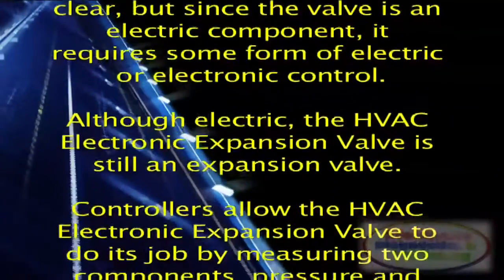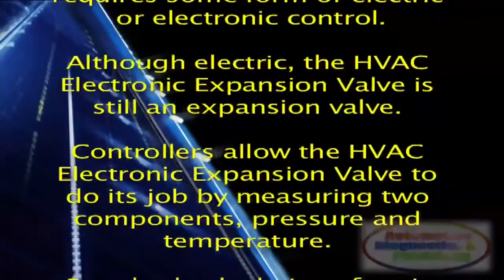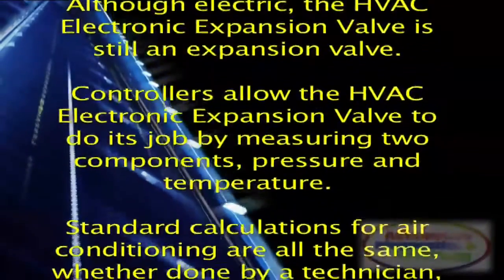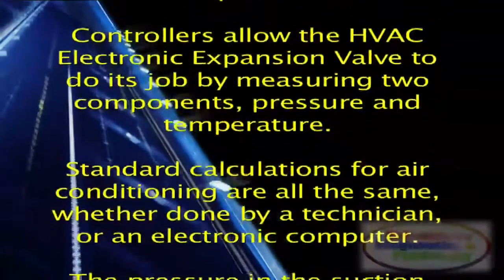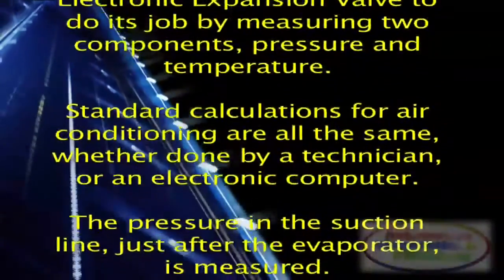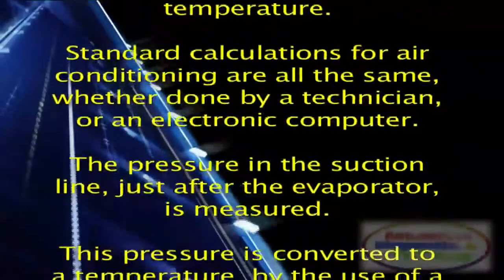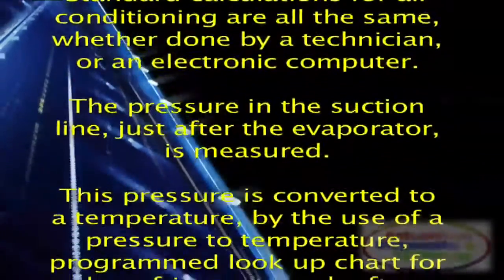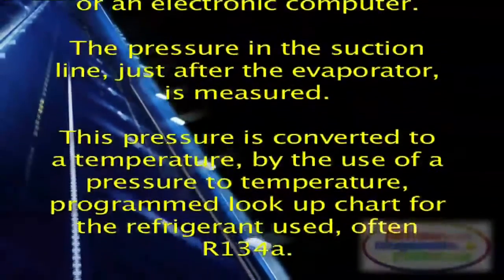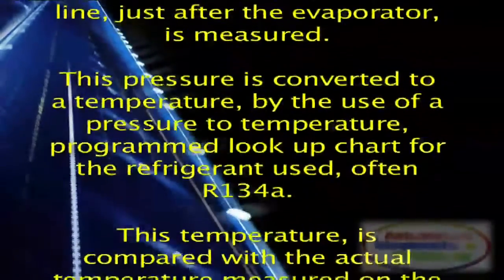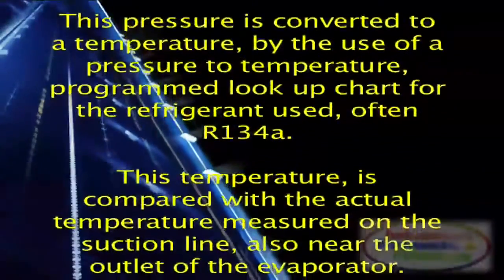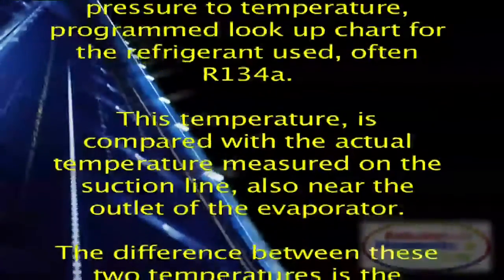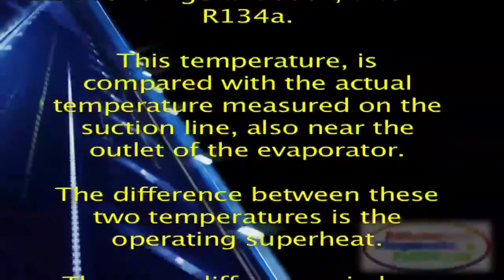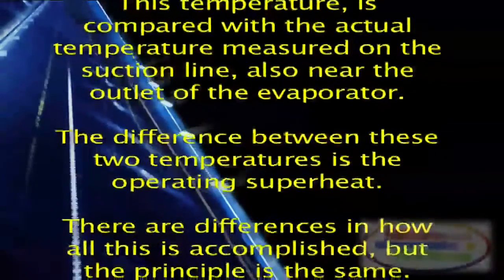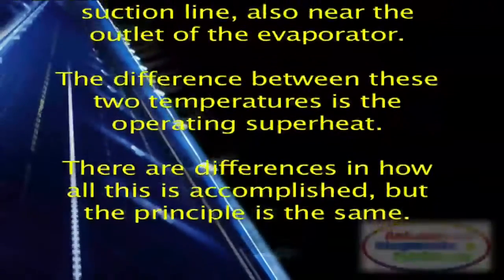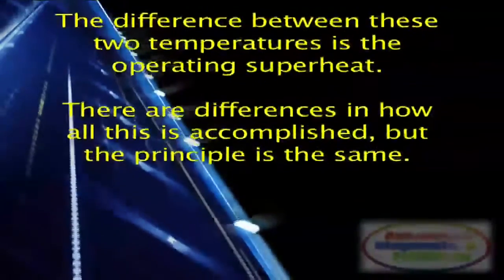Controllers allow the HVAC electronic expansion valve to do its job by measuring two components, pressure and temperature. Standard calculations for air conditioning are all the same, whether done by a technician or an electronic computer. The pressure in the suction line, just after the evaporator, is measured. This pressure is converted to a temperature by the use of a pressure-to-temperature programmed lookup chart for the refrigerant used, often R-134a. This temperature is compared with the actual temperature measured on the suction line, also near the outlet of the evaporator. The difference between these two temperatures is the operating superheat.